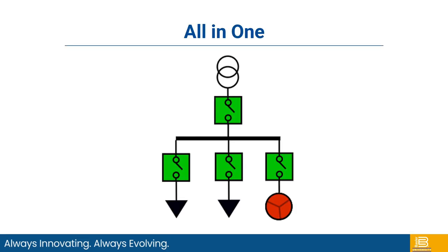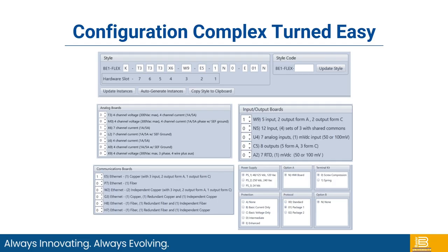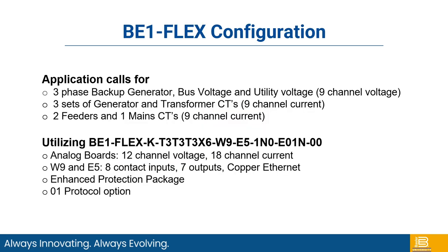And then last but not least, the all-in-one, where you have a main breaker, a generator breaker, and 2 feeders. So for this particular application, you need the 3 T3s and an X6. So 4-channel current, 4-channel voltage, and 7-channel current, along with a W9 and an E5 that gets you 8 inputs, 7 outputs, along with your power supply and the enhanced protection again, and the protocol package 01 with Modbus and DNP3.